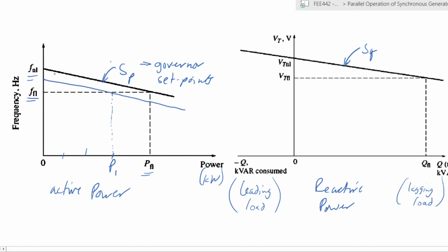Close enough. Okay, so what you would do is you would then have a new value of no load frequency at which you would set your governor. All right? So what that means is, if, for example, imagine that your governor is running without being connected to any load. It is isolated, it has been disconnected from everything. It is just the prime mover rotating the alternator, and you're measuring the frequency that is coming out of the terminal points. At no load, at zero here, when you're supplying no load in those conditions, you could then set the governor to adjust the speed that it is outputting, right?